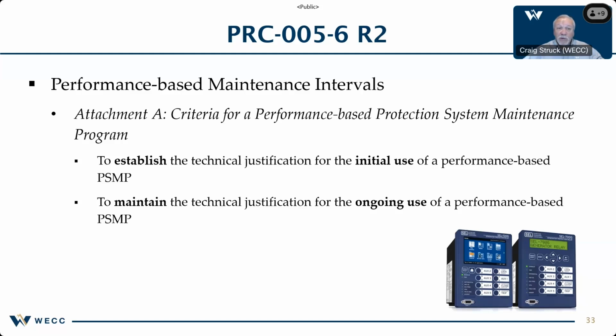So what are the differences between time-based and performance-based intervals? Time-based intervals are externally prescribed maximum maintenance or testing intervals for components or groups of components. The intervals may have been developed from prior experience or manufacturer's recommendations. The maintenance intervals are fixed and may range from months to years. Performance-based maintenance intervals are established based on analytical or historical results of time-based maintenance failure rates or of similar components. With performance-based maintenance, some level of time-based maintenance is generally followed. Statistical analysis accompanied by adjustments to maintenance intervals are used to justify continued use of performance-based extended intervals when failures occur infrequently. Performance-based maintenance is not commonly used in the Western interconnection.